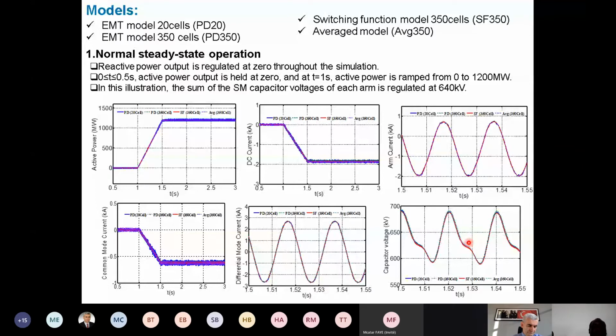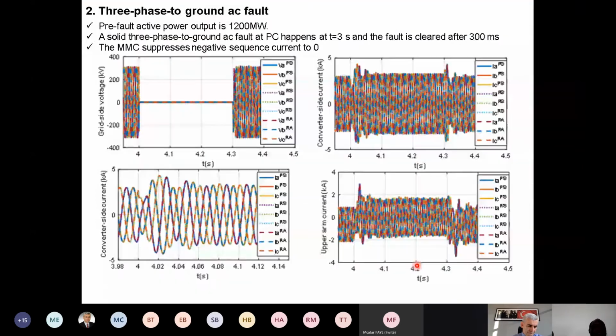also all similar. And here, this is the case of a 3-phase to ground fault. This is the grid side voltage where the fault happened, which is solid. You can see here, this is the converter side current, which is well controlled with the control system we displayed earlier. And this is the zoom of this current around this point. You can see all the models largely agree. And this is the arm current. You can see also the arm current is well controlled.